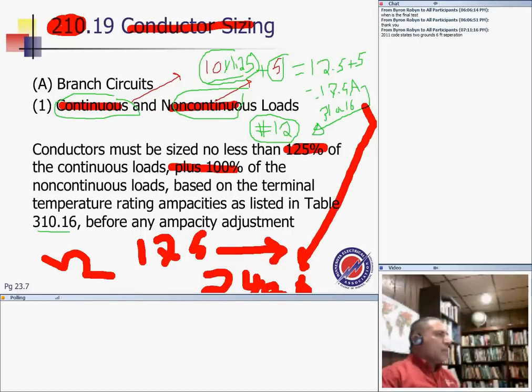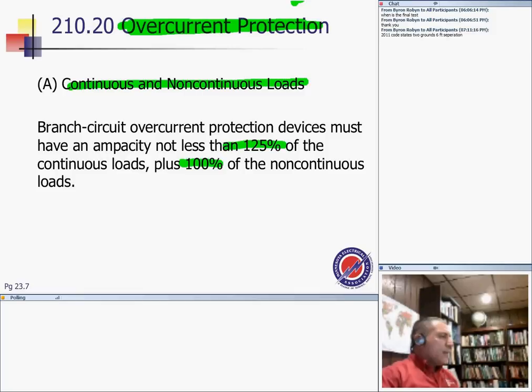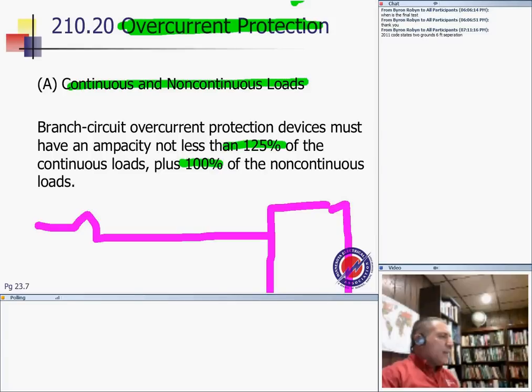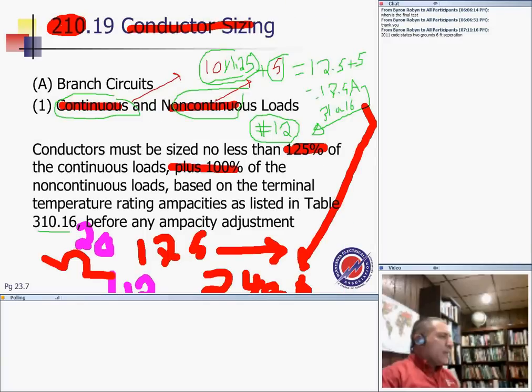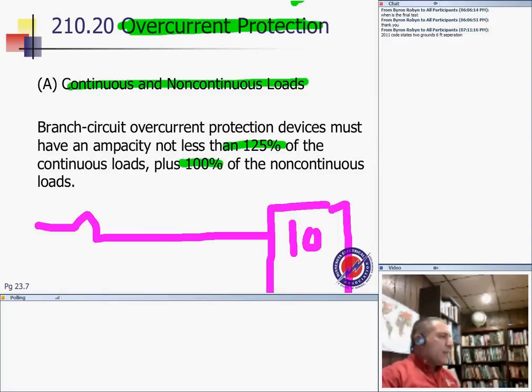So for the example that I just showed you, in this case you can have a load. Here's my load. You're going to have a 20 amp circuit breaker feeding a number 12 conductor to feed a load. The load is the 10 amp plus 5 amp, continuous and non-continuous. Any question guys about this? How is the conductor and protection device sized? Here's my machine, which has a 10 amp continuous, C, and 5 amp non-continuous. So sizing, as you guys have said, I came up with number 12 conductor and 20 amps.